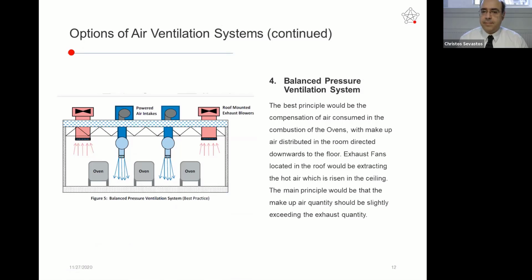Exhaust fans, powered, located in the roof, would be extracting the hot air which has risen to the ceiling. The main principle would be that the makeup air quantity should be slightly exceeding the exhaust quantity. So we are applying a positive pressure here. We are applying the proper air supply in order for the ovens to operate efficiently. We are going to refer to the calculations of how we are going to apply a positive pressure inside the room.